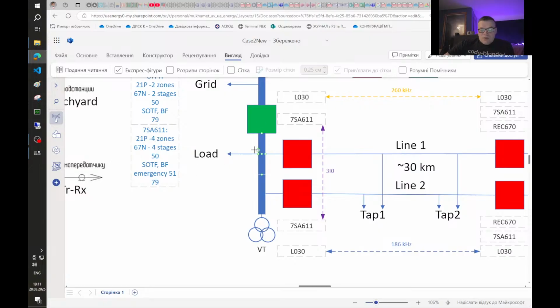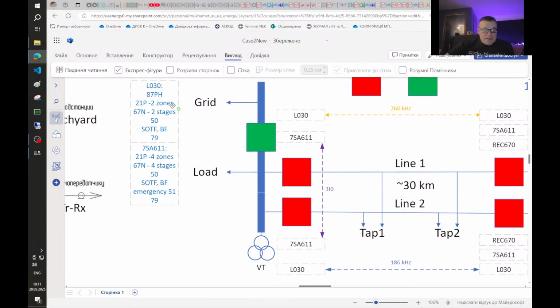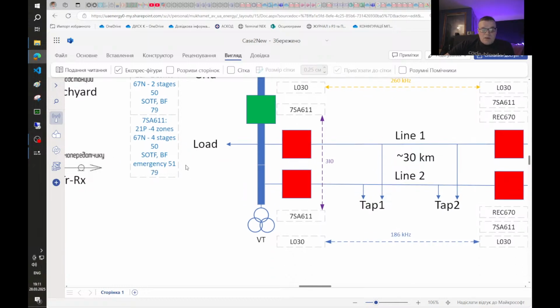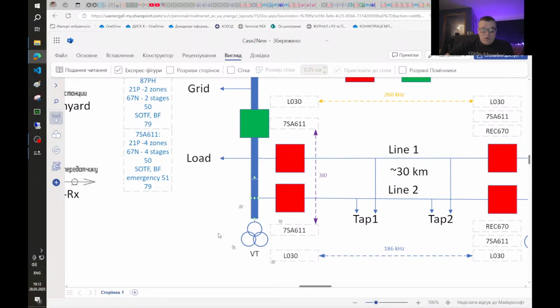If we talk about the Siemens device, there are 4 zones of distance protection, 4 stages of earth fault protection, and pretty much the same as this guy, but it also has emergency overcurrent, time overcurrent protection. It is enabled in case of loss of VT.